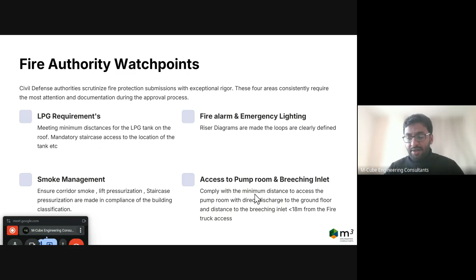Also, the breaching inlet should be somewhere very visible, because in some previous or older buildings, the breaching inlet was not at the main entrance - it was somewhere on the service corridors or behind the building, not accessible. Now it's very stringent, and they particularly look at this point to ensure breaching inlets are within less than 15 meters from the road, so the fire truck can easily access and connect to the breaching inlet. These are some of the watch points related to firefighting systems that we need to be careful about.